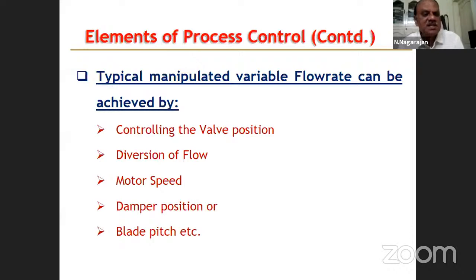Okay, suppose the same heat exchanger example I will tell you. If suppose the oil temperature is going high in spite of your control, what will you do? You divert part of the inlet oil, bypass the heat exchanger, connect it directly to the outlet line. So some cold oil is going there, it will mix and then control the temperature. So this is called diversion of flow. Usually comes in the bypass controls. Motor speed, if you have an air cooler, a heat exchanger where cooling is affected by fans, you can vary the motor speed, thus vary the airflow and control the heat exchanger duty.